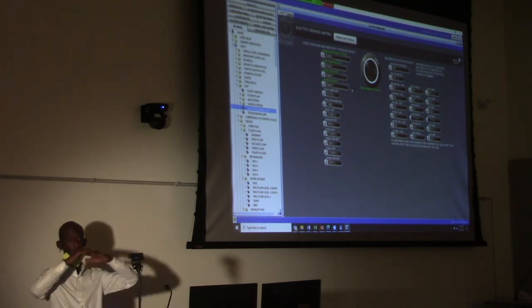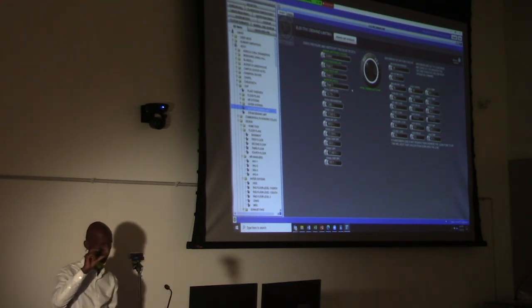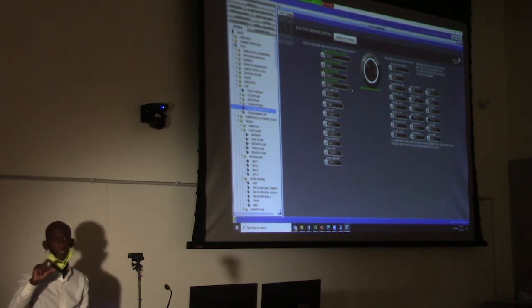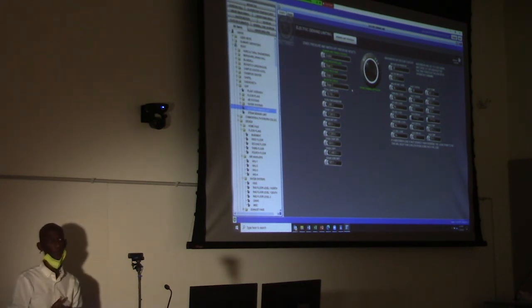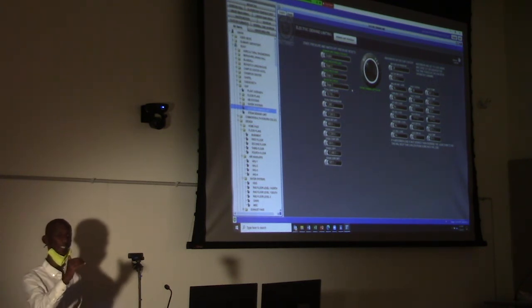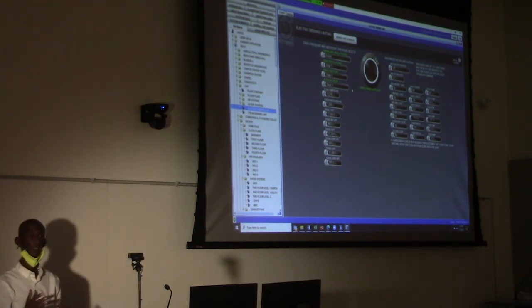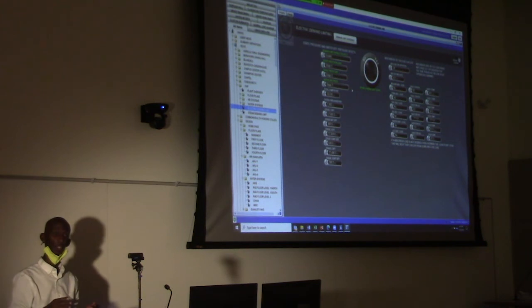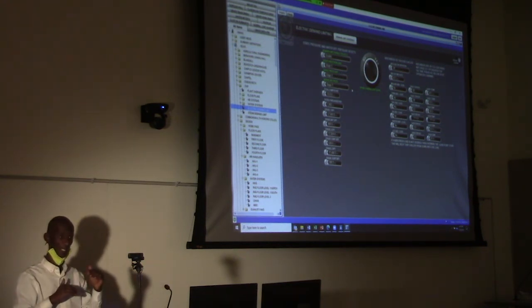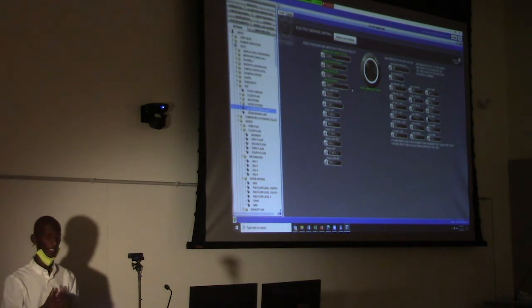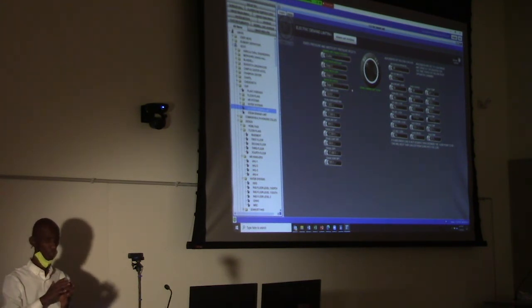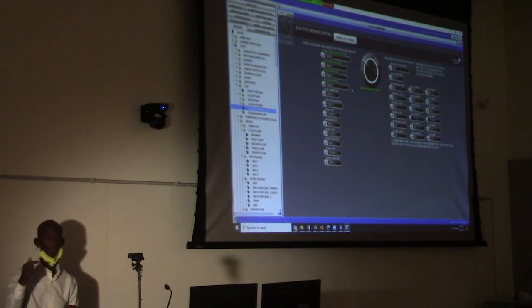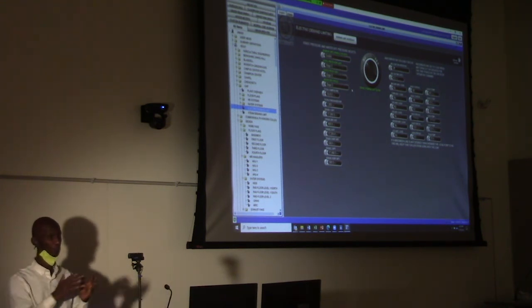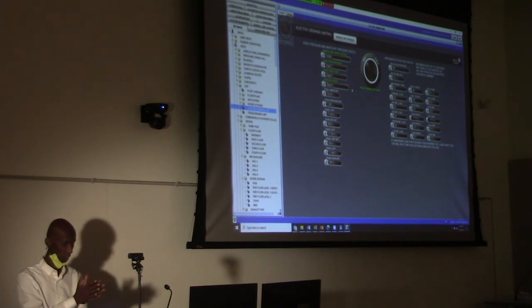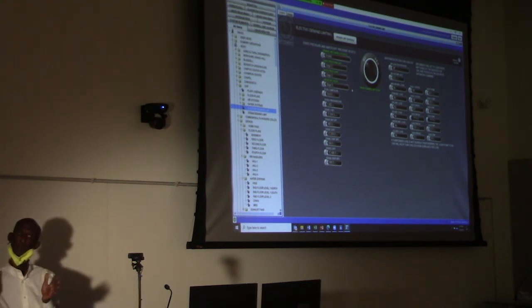So what we did was just set back the temperature to 55 degrees to avoid any issue, and then we were able to save a lot of energy. Plus, the good part was not only that. When you have equipment running, you have to have people maintaining it. So when we set it back, at least we have less equipment running. And April through June was good. Also, after we went through that cold weather, we could turn off some equipment.